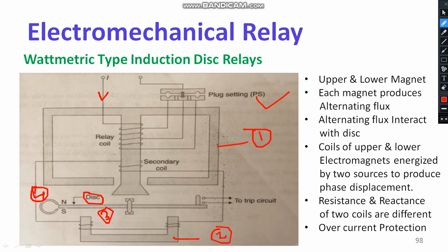Look at the secondary coil, which is directly connected to the lower magnet. Here, flux phi-1 is generated on the upper side, and on the lower side, flux phi-2 is generated. Both fluxes interact, and the difference in flux generates displacement of the disc — that means there is torque production at the disc. To stop the disc in a desired position, a braking magnet is used. With respect to the movement of the aluminium disc, the tripping circuit is activated. The interaction of phi-1 and phi-2 is most important — with respect to current, phi-1 varies, which also depends on phi-2. The interaction of fluxes drives the movement of the aluminium disc, thereby activating the tripping circuit.